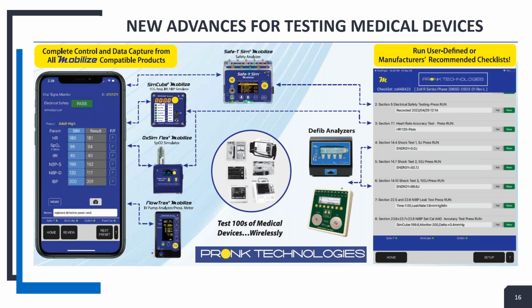In the case of the manufacturer level procedures we've created, you have only the flexibility to modify things the manufacturer says are optional tests. An example of that is maybe you have Wi-Fi, you're using it on the defib. Okay, well, let's do that test. But if you're not, I'm going to click on the options buttons here and turn off that test. And you could do this for other things as well. It's up to you to design the procedure the way you'd like. These manufacturer level ones are designed so that if the manufacturer says you have to do it, we will not give you the option to not do the test, but these all could be modified.